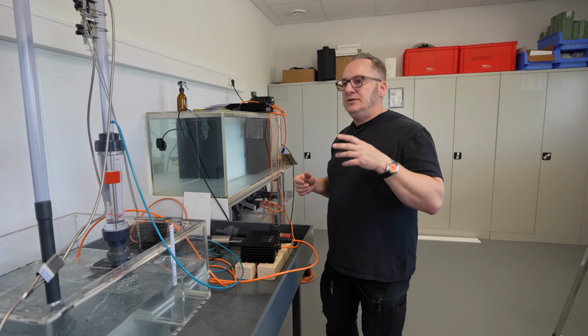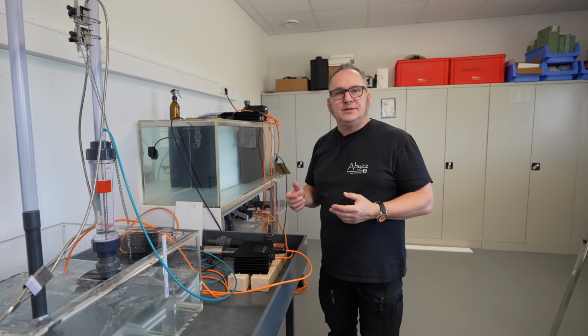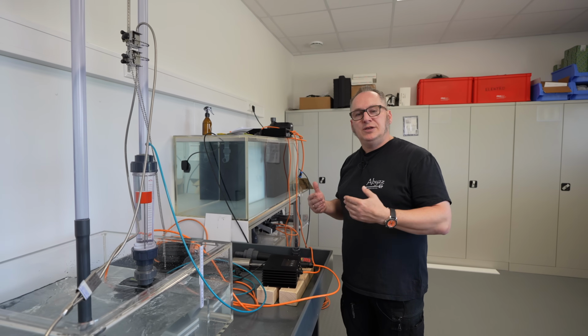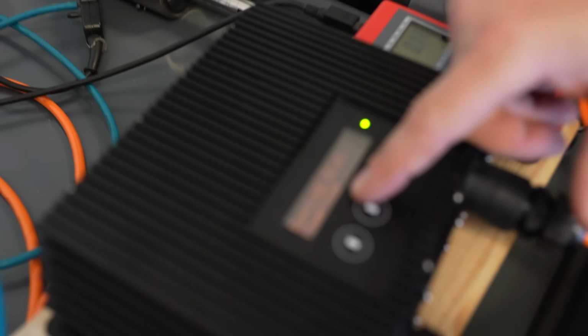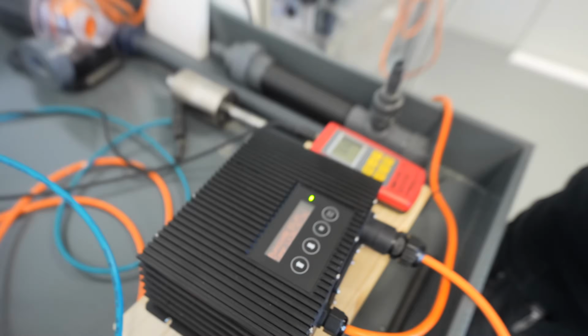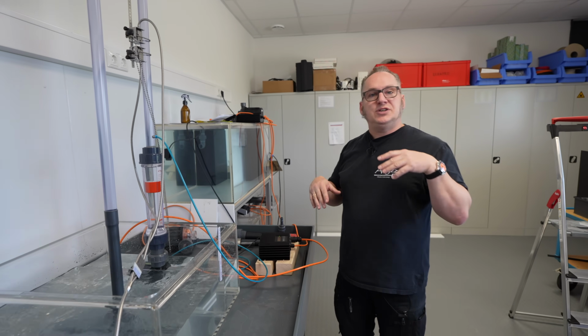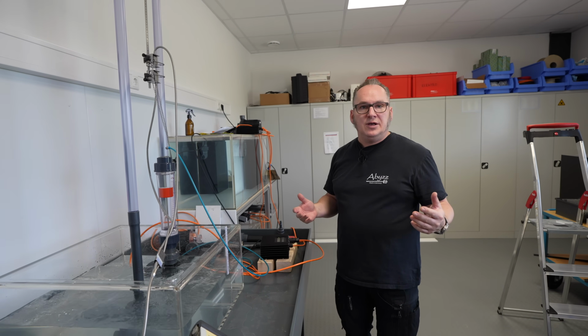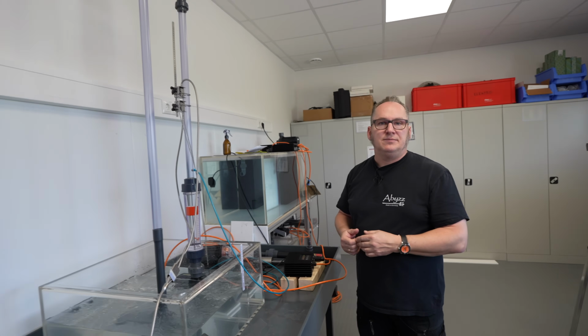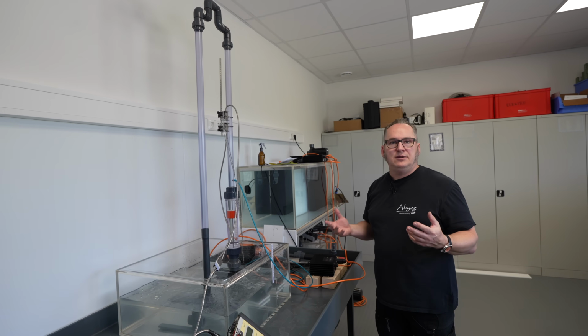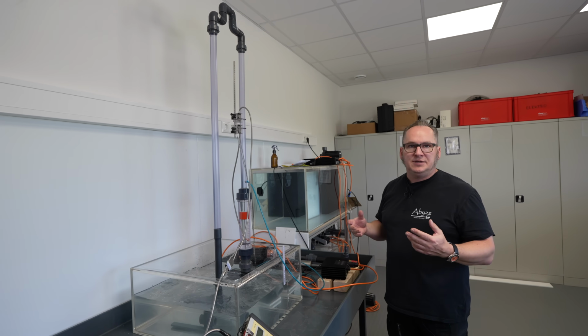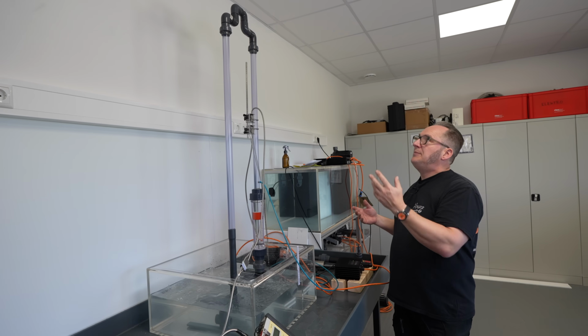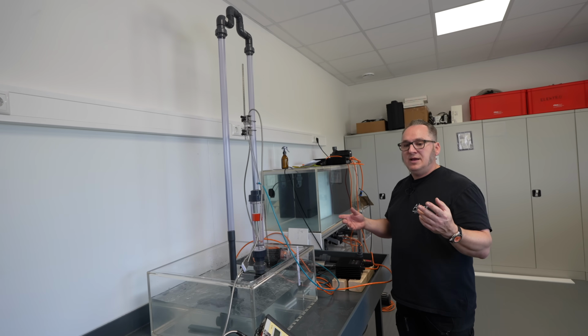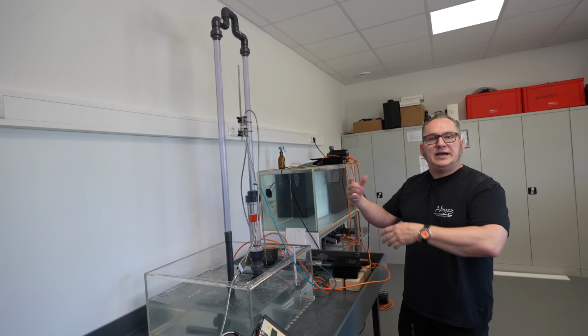So that's roughly 60% more power usage to have the same turnover. See, it switches from 82, 83. That's for the same value. So just because you plumbed the system wrong, you're using 60% more energy, and that's where it becomes really relevant to have the right diameters and the right plumbing. This usually happens in retrospect. So you have a system, then you need to replumb it, or you need to add something to it.